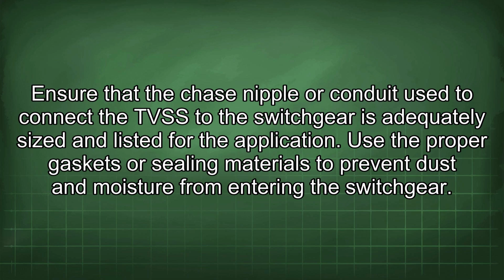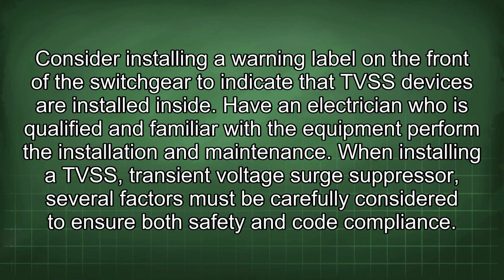Ensure that the chase nipple or conduit used to connect the TVSS to the switchgear is adequately sized and listed for the application. Use the proper gaskets or sealing materials to prevent dust and moisture from entering the switchgear. Consider installing a warning label on the front of the switchgear to indicate that TVSS devices are installed inside. Have an electrician who is qualified and familiar with the equipment perform the installation and maintenance.